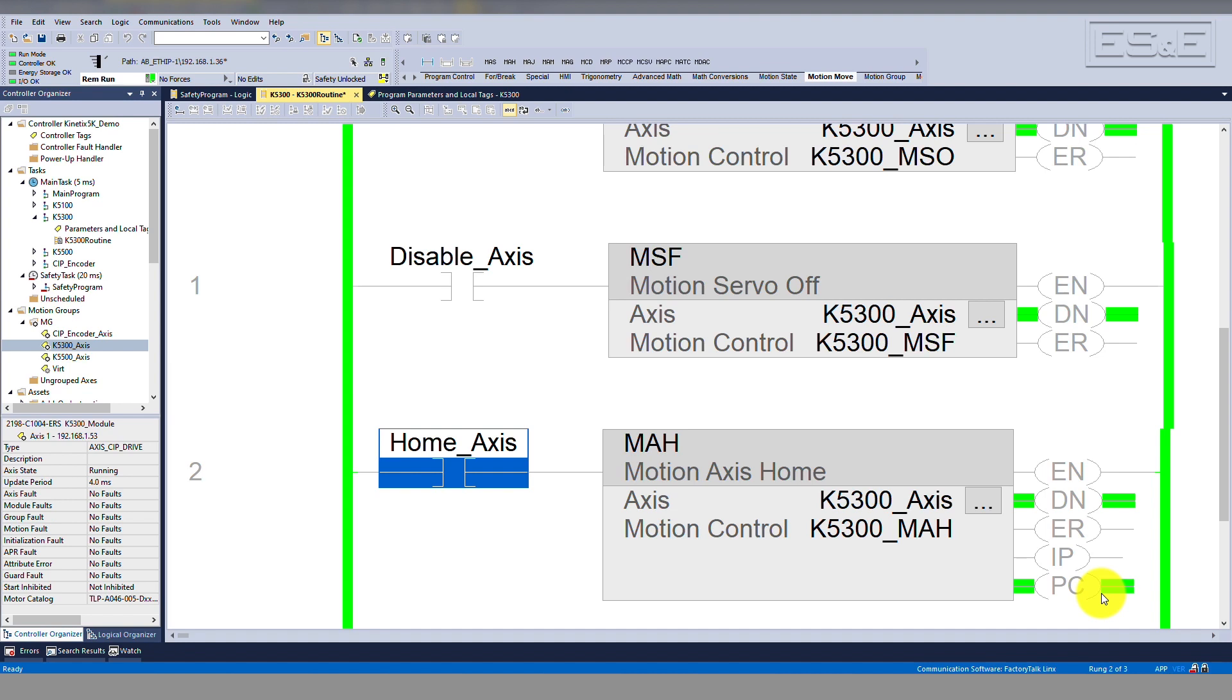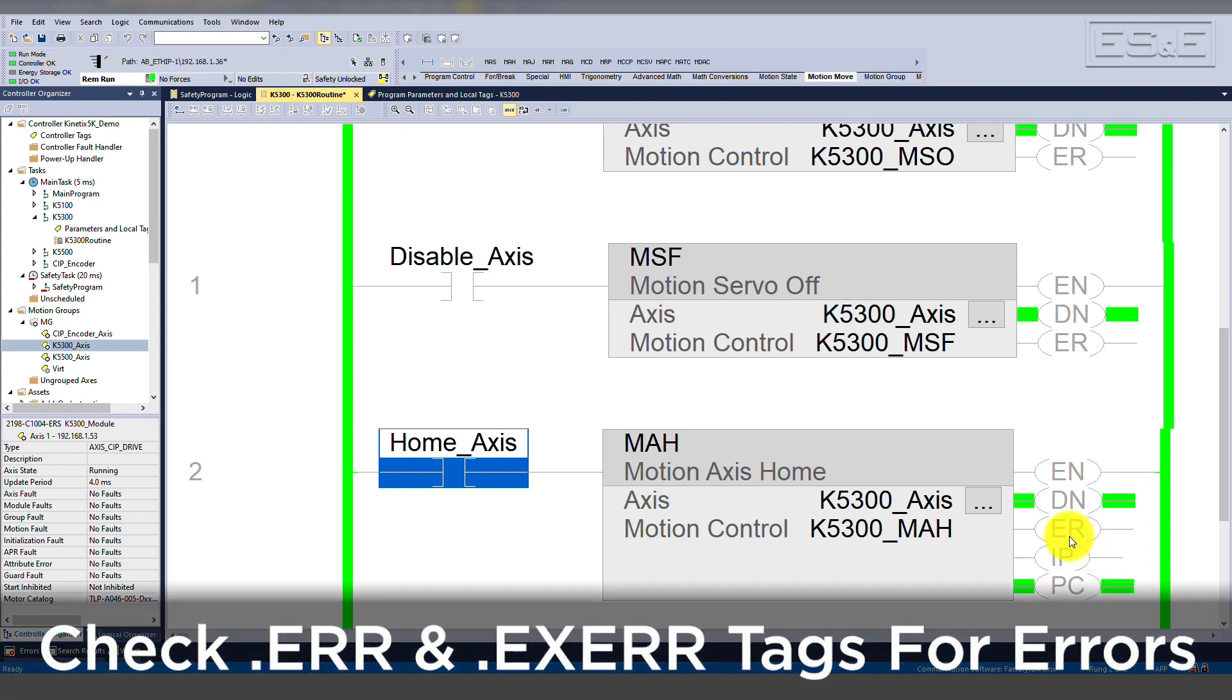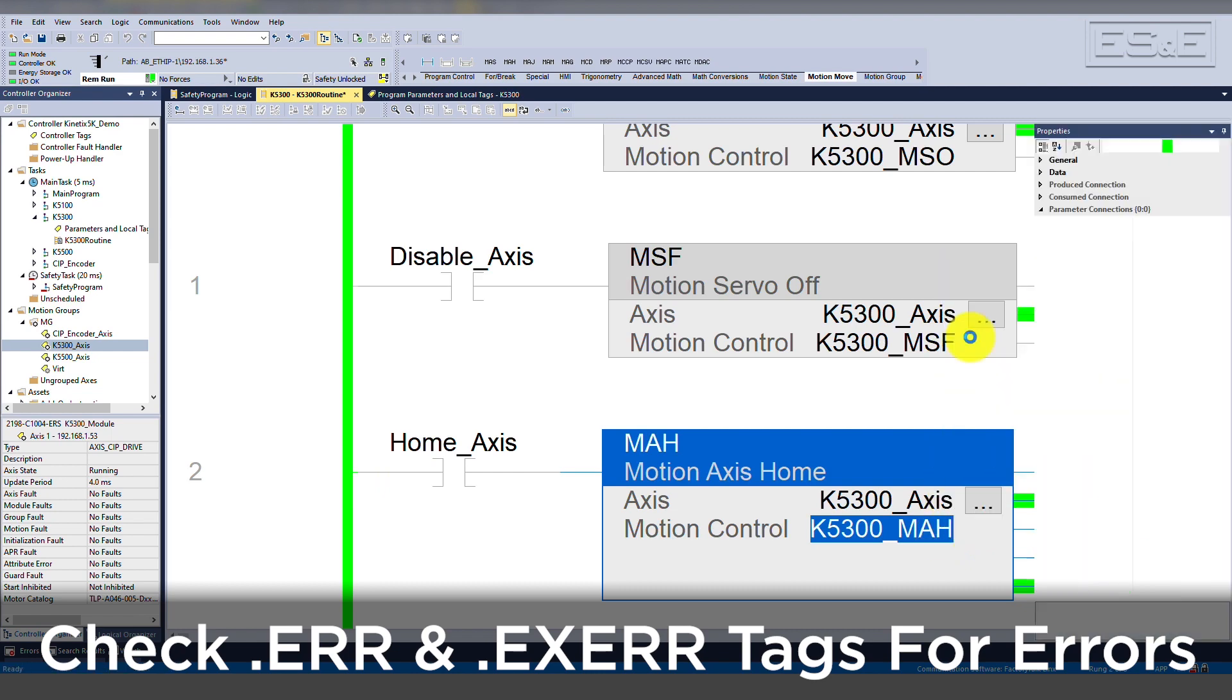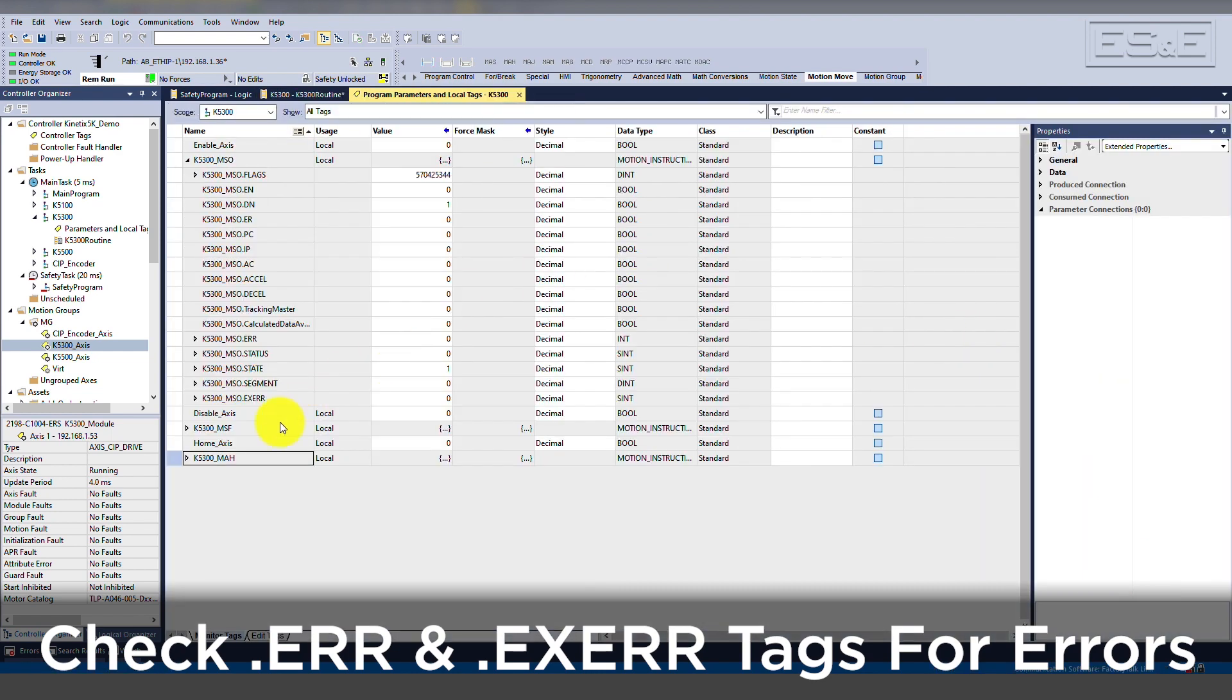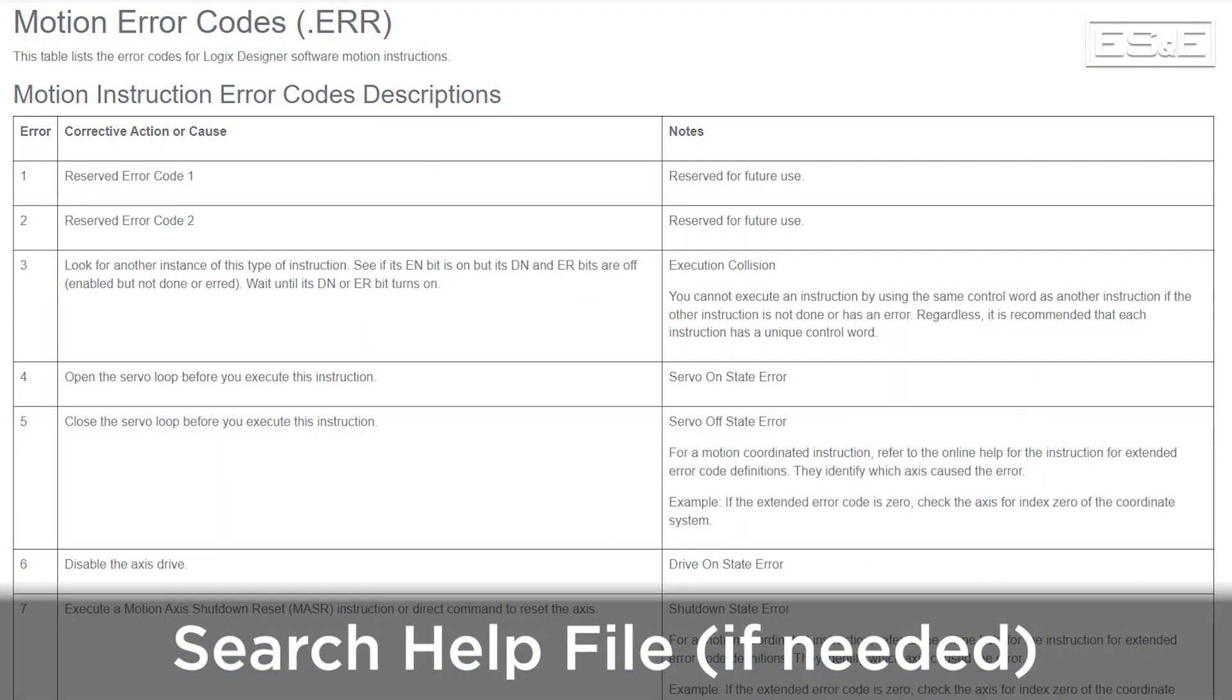If the instruction is executed and the ER bit goes true, then you can look at the .err and .exerr tags to see what specific error you are getting. You can then search for the error in the help file to determine what caused the instruction to error.